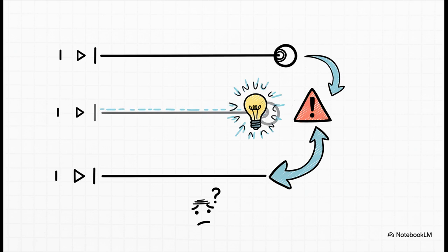The PLC doesn't turn them off. It doesn't even look at them. They are just frozen, stuck in whatever state they were in the last time that code was actually scanned. And let me tell you, this is a massive, massive source of confusion and can be a total nightmare to troubleshoot if you're not ready for it.